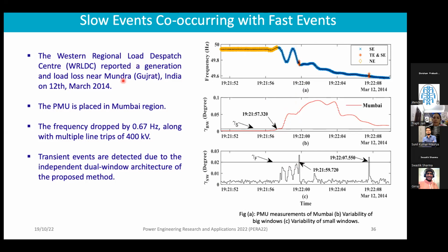This event actually happened near Mundra in Gujarat. The Western WRLDC reported a generation and load loss near Mundra on 12th March 2014, where the frequency dropped by 0.67 hertz. These transient events are detected due to the independent dual window architecture of the proposed method.